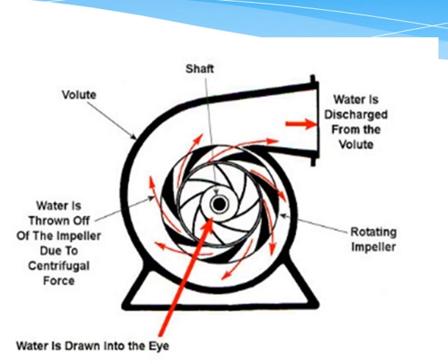Now, going back to Bernoulli's principle, a decrease in velocity is going to result in an increase in pressure. So the pressure in this pump casing is increased twofold. It's increased as it comes off of the impeller and smashes into the walls of this pump casing. And then as it travels through this volute pump casing, that area expands, the velocity decreases, and therefore the pressure increases. So the water that leaves this pump now is at a lower velocity, higher pressure.